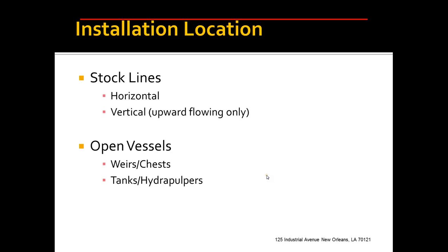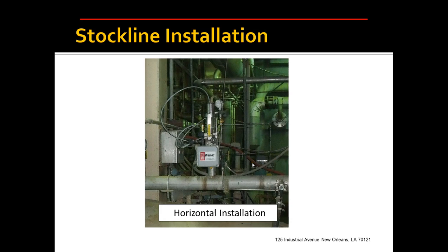Installation locations. Well, we have a variety of different configurations that could accommodate almost any location in your mill. For stock lines, we have horizontal and vertical flowing lines. We recommend that they be upward flowing only because with downward flowing lines, you never know if they are full or not, and they need to be full. We can also do inclined lines. We have configurations which are suitable for open vessels, weirs, chests, tanks, and hydropulpers. This is an example of a horizontal installation.